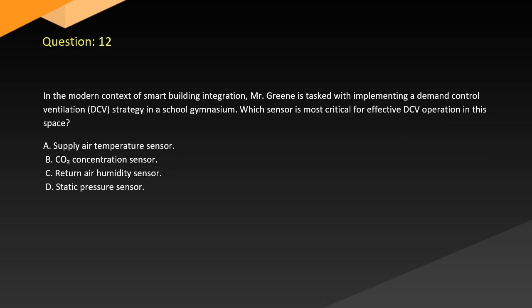Question 12. In a modern context of smart building integration, Mr. Green is tasked with implementing a demand control ventilation (DCV) strategy in a school gymnasium. Which sensor is most critical for effective DCV operation in this space? A. Supply air temperature sensor. B. CO2 concentration sensor. C. Return air humidity sensor. D. Static pressure sensor.